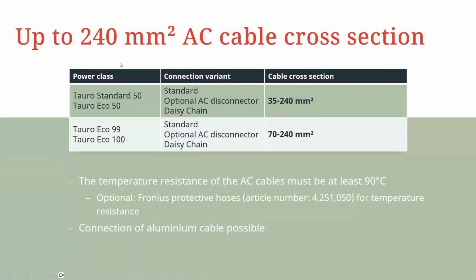It's possible, as mentioned in the previous slides, to have up to 240 mm squared cable cross-section. For the connection variant available for the standard option with AC daisy chaining for the Tauro 50s, that's for the Eco and the standard, you can have cross-sectional area of 35 to 240. Then for the larger power classes, you can have them from 70 to 240 squared.